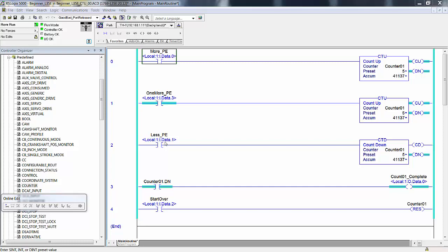Well, now you have some interesting behavior, don't you? And I think you can explain this one. Again, we have a scan counter. What's happening here? This rung is false. So the false execution of a count up is to reset its one shot that allows it to increment only once on a false to true transition. But the very next rung is true, so it increments. And then the next scan around sets it to false, sets it to true, sets it to false, sets it to true.